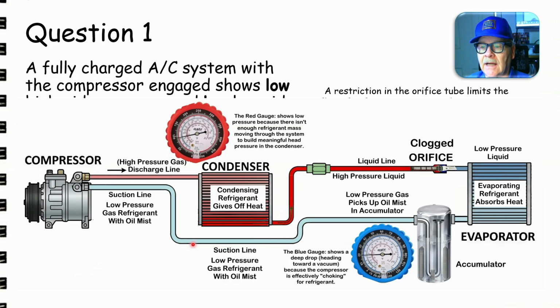The suction line is the big line. It's the one that's always cold. If you're charging one up, like on a tractor or a front end loader that's got an air conditioned cab, and you don't know how much refrigerant to put in it, just keep putting refrigerant in until this suction line is cold all the way to the compressor. When it's cold all the way to the compressor and nice and sweaty like a glass of tea, then you know you've got enough refrigerant in it.